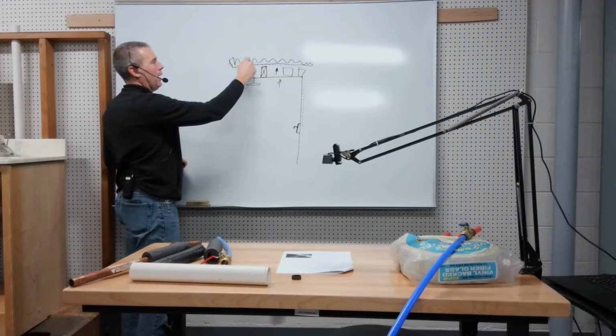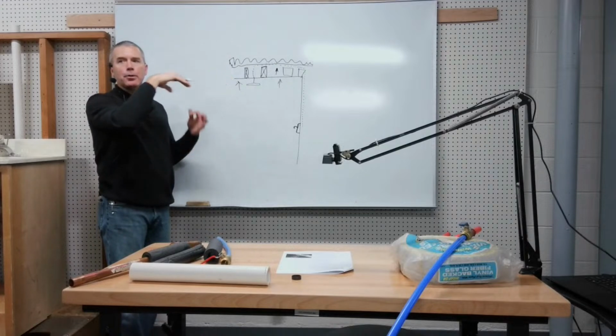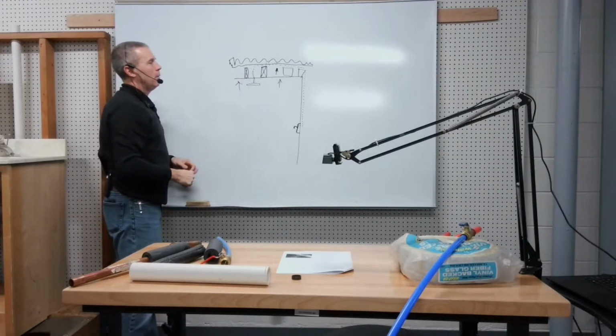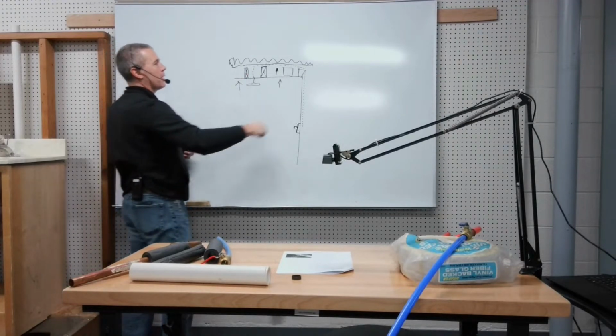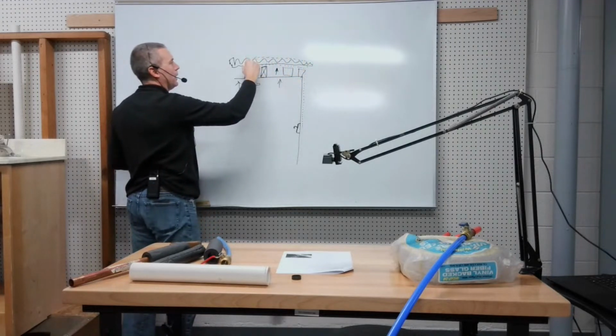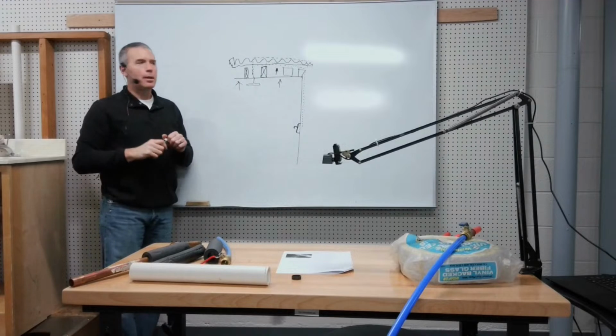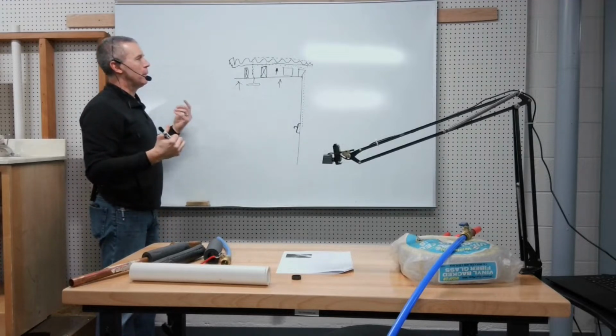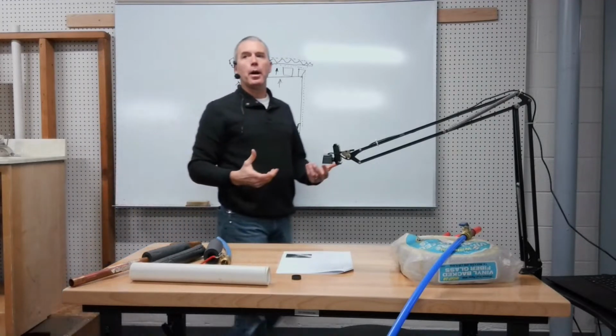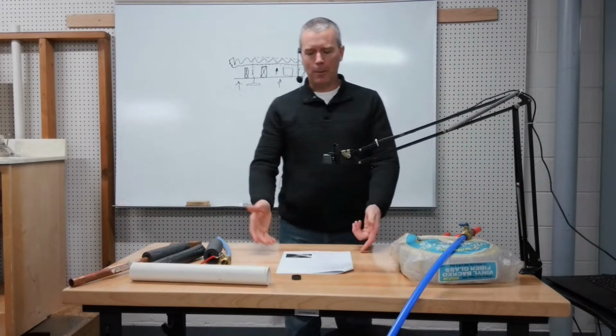A lot of times, I'll throw this insulation down on top of it, and then they'll blow in insulation on top of it. So it's kind of like double protected. And that's how you can get away with running a water line up there. And like we were just talking about, frozen lines. In Texas, they run their water lines up and then down. And when this is open to anything that's colder than 32 degrees, boom, they've got trouble. It splits, it ruptures, it freezes, and causes all kinds of trouble. And I think they even had trouble with city water rupturing because it's not designed for cold weather, unfortunately.